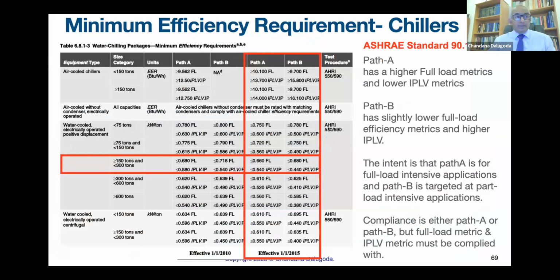Now, in the pathway to reduction of energy, how to select chillers? Very quickly, I will show you. ASHRAE 90.1 gives this particular table to select chillers. Say water-cooled chillers, 75 tons, 75 to 150, 150 to 300, and so forth. Your efficiency is given in path A and path B. Path A is the full load metrics. Path B is the part load metrics. That is, if chillers are running for full load, block load, we select this energy efficiency level. If the chillers are running for part load, we use this, or we have to use both combined.